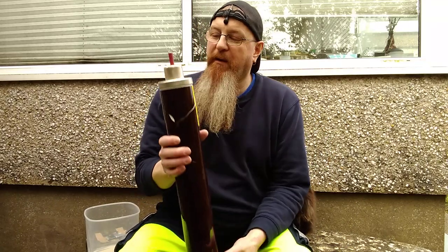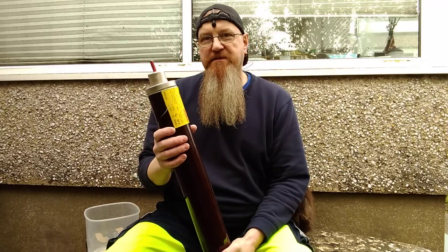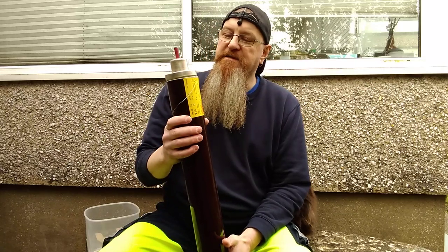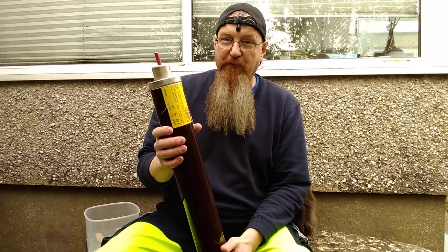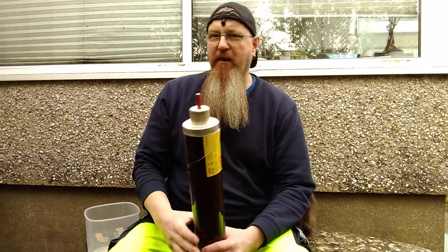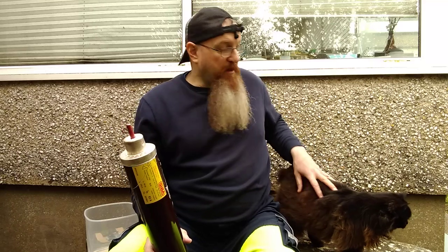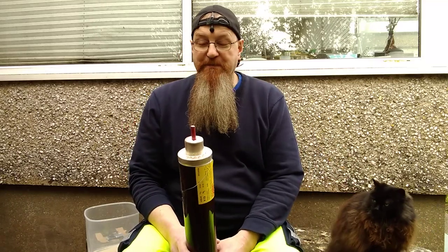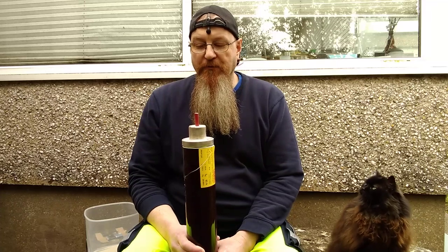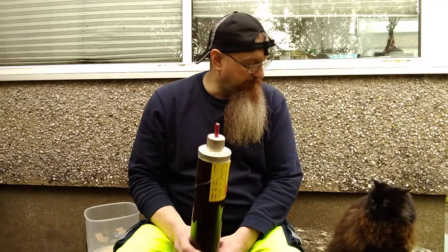This fuse was sent to me by Chris, who works at a company that makes substations and control equipment. This is one of a set of three fuses from a solar farm in the UK. Last year, there was so much solar power that it overheated one of the substations, caused the transformer to split, and one of the fuses let rip with quite a big bang.